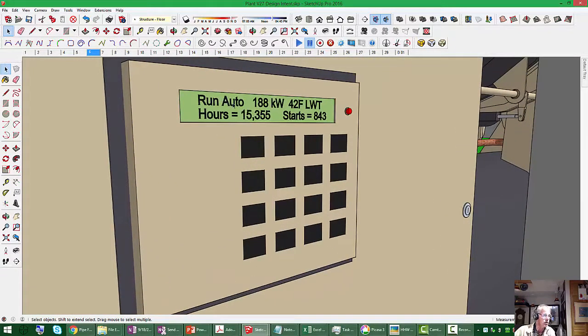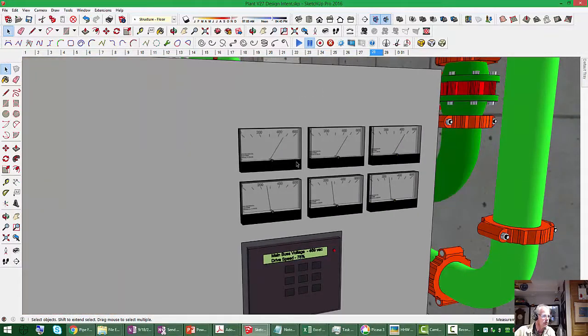It says it's running, it's in auto, it's using 188 kW. Okay, and if we looked at its starter, we discover, well, yeah, there's 480 volts on it, and it's up in the 200, 300, 260 or so amps on it. So yeah, it's definitely using some power. And so then the question becomes, well, how close to full load do we think that is?